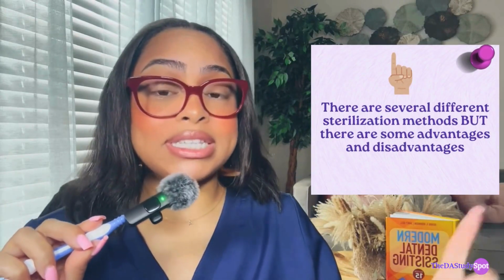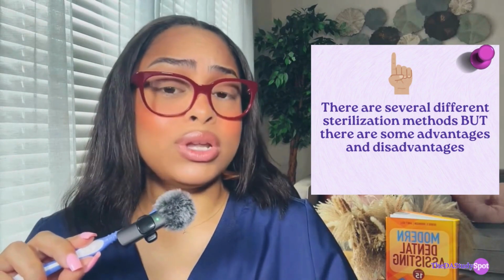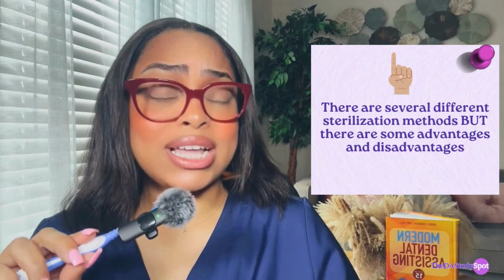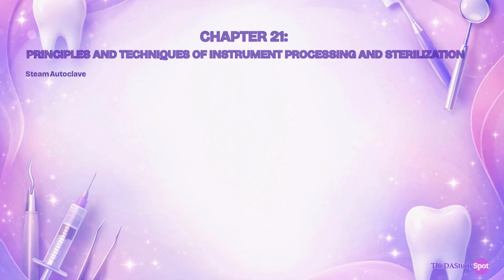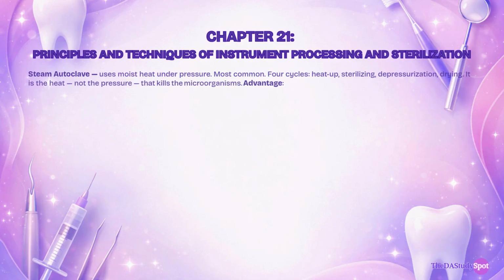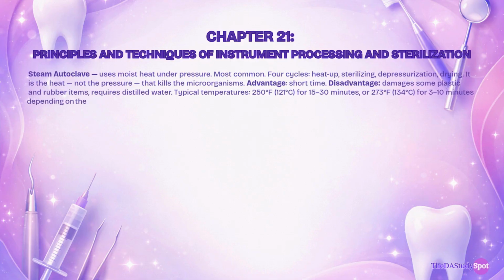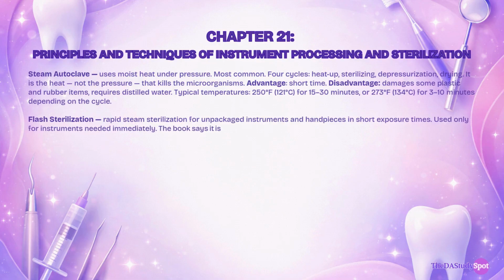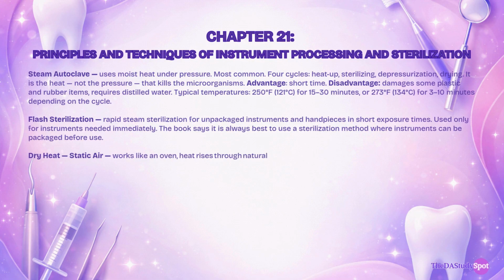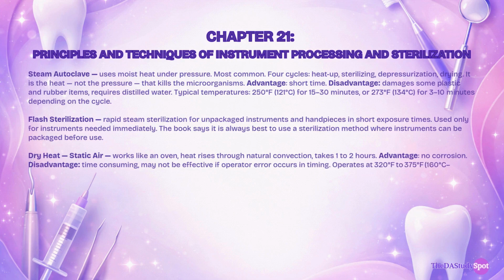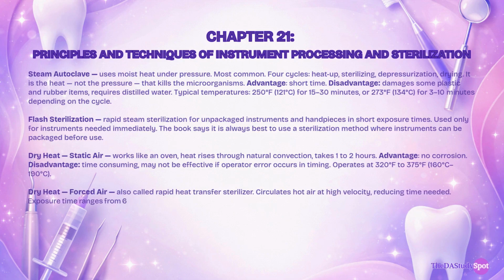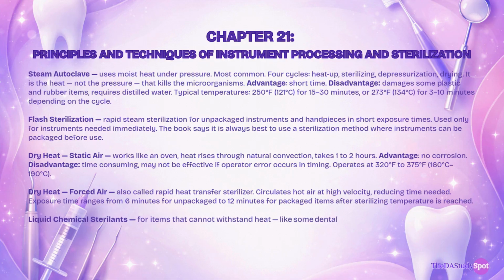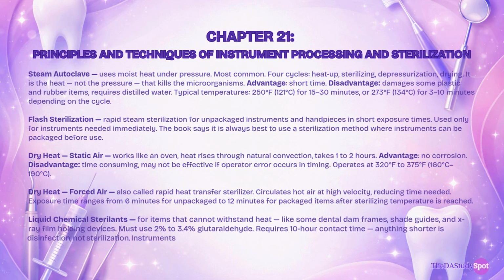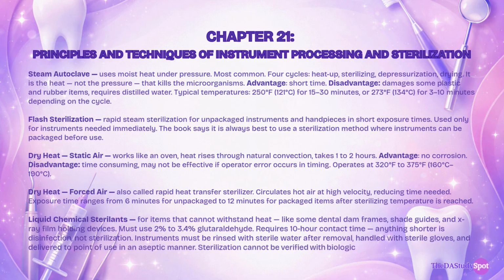Now for the big one, sterilization methods. The book not only covers these, but it gives advantages and disadvantages side by side. So for the steam autoclave, this uses moist heat under pressure. It's the most common and has 4 cycles: heat up, sterilizing, depressurization, drying. It is the heat, not the pressure, that kills the microorganisms. The advantage, short time. Disadvantage, it damages some plastic and rubber items and it requires distilled water.